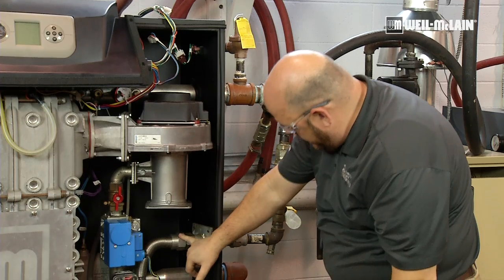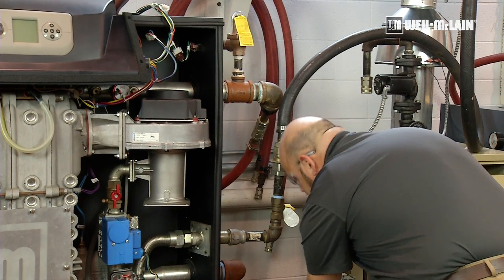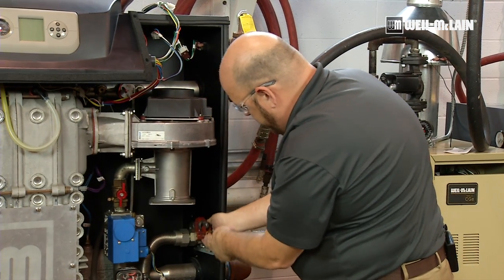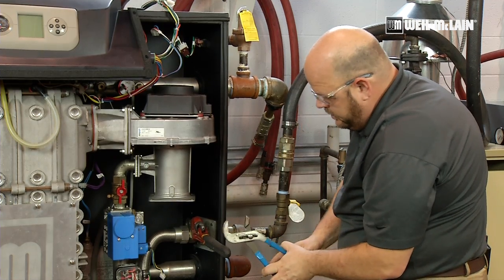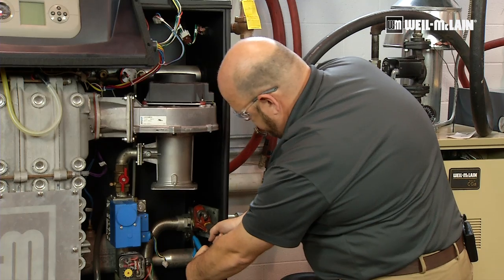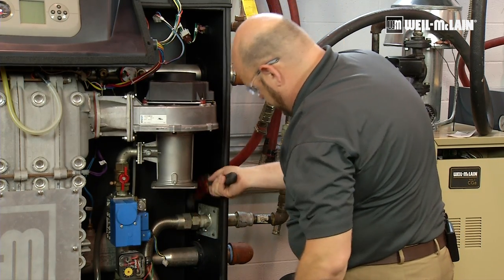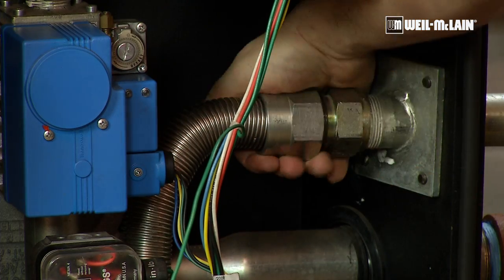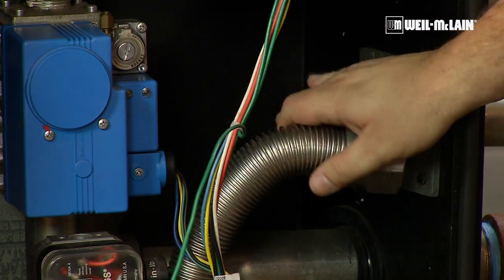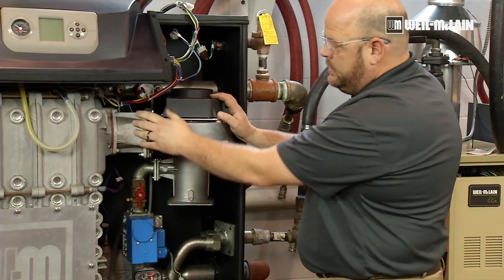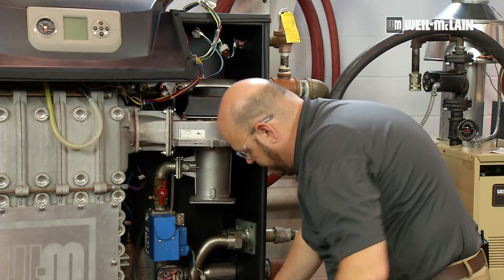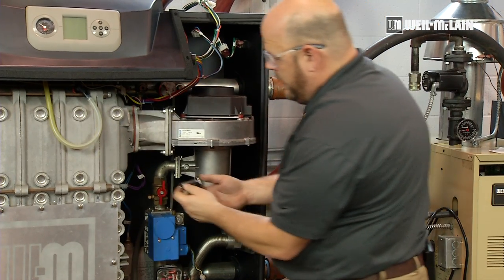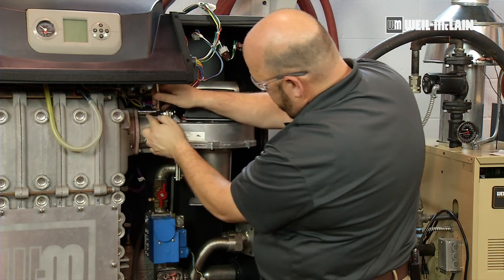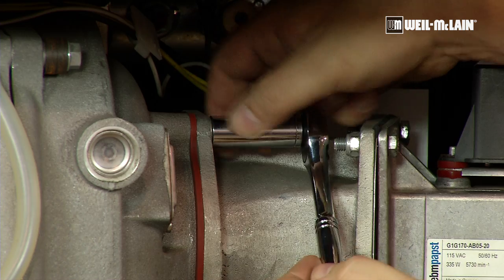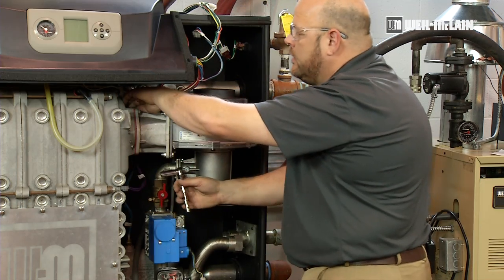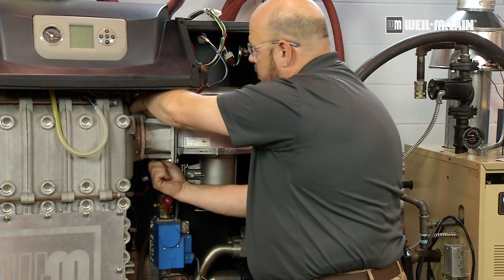And now we have a compression nut for our inlet gas. In order to keep us from spinning this, we'll put a wrench on each side of it, and then break the compression nut loose. So this leaves the blower and the gas valve and the switches hanging from the three 13mm nuts. So with a 13mm socket, we can break it loose at the top, break it loose in the bottom, and then the third is in the far back here, which we can break loose.